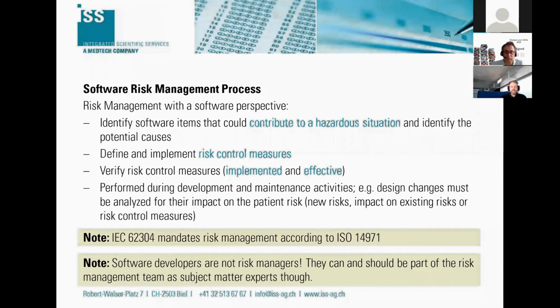Risk management. This is part of the overall risk management of the device because the 62304 mandates the use of the 14971 risk management standard. There are some exceptions, but they're not worth talking about.